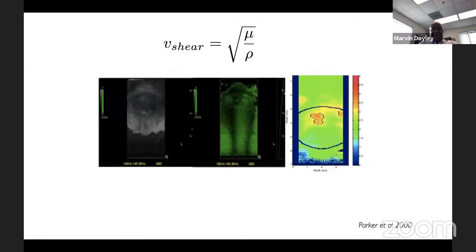All right, here's another. The example that I just showed a while ago is all quasi-static. Now, if we look at harmonic elastography, this is what it would look like. As I said before, what we're going to do here is basically put a low frequency vibrator, you can use a speaker, and you just introduce shear waves. In this case, Professor Parker is looking at the shear wave speed as it moves across, and he's using classic Doppler signal processing to measure that shear wave propagation across this tissue.